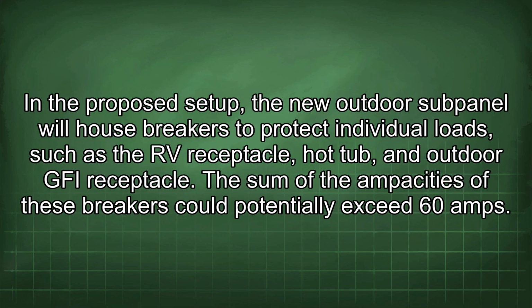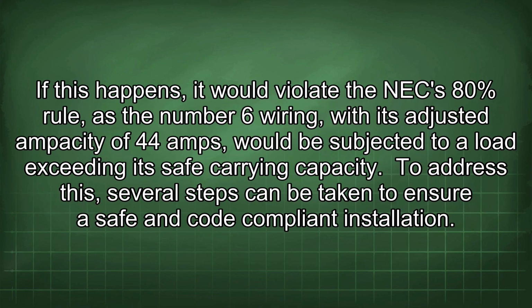In the proposed setup, the new outdoor subpanel will house breakers to protect individual loads, such as the RV receptacle, hot tub, and outdoor GFI receptacle. The sum of the ampacities of these breakers could potentially exceed 60 amps. If this happens, it would violate the NEC 80% rule, as the number 6 wiring, with its adjusted ampacity of 44 amps, would be subjected to a load exceeding its safe carrying capacity. To address this, several steps can be taken to ensure a safe and code-compliant installation.